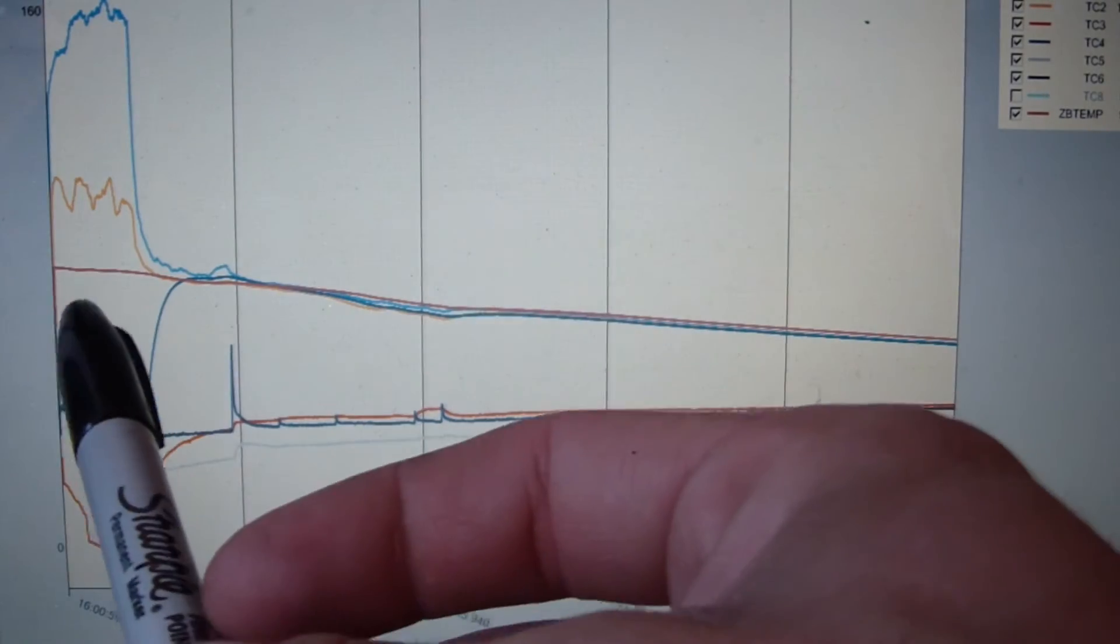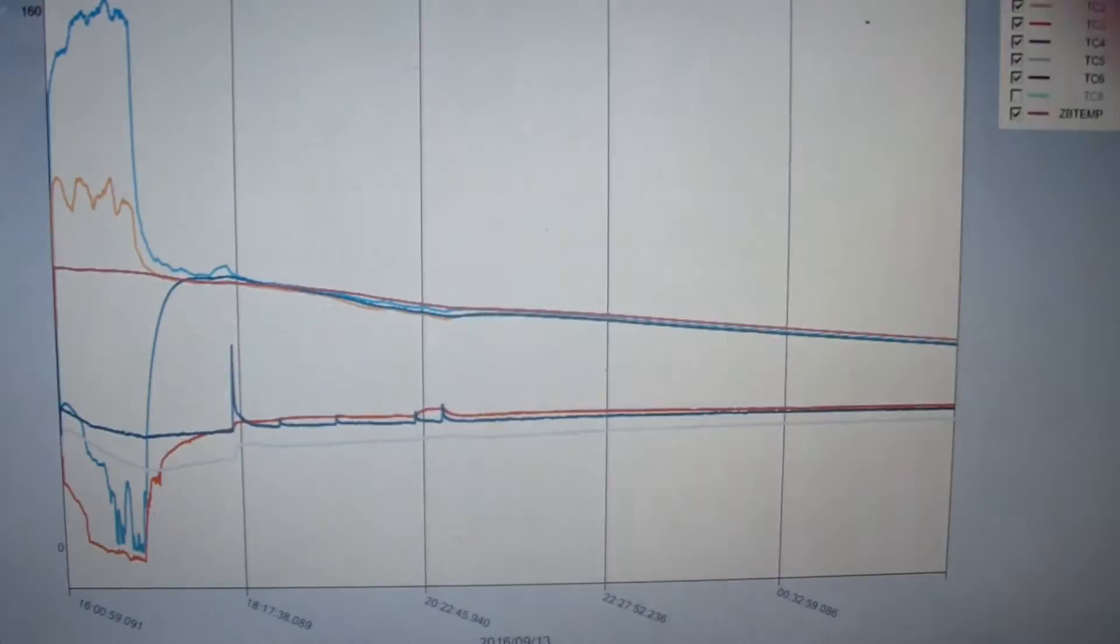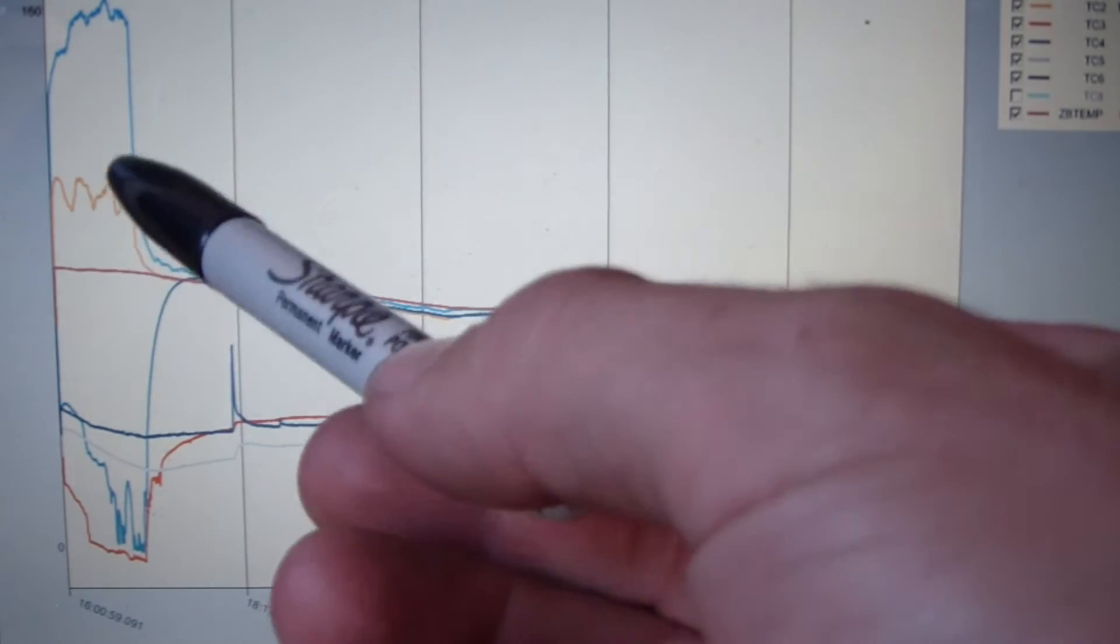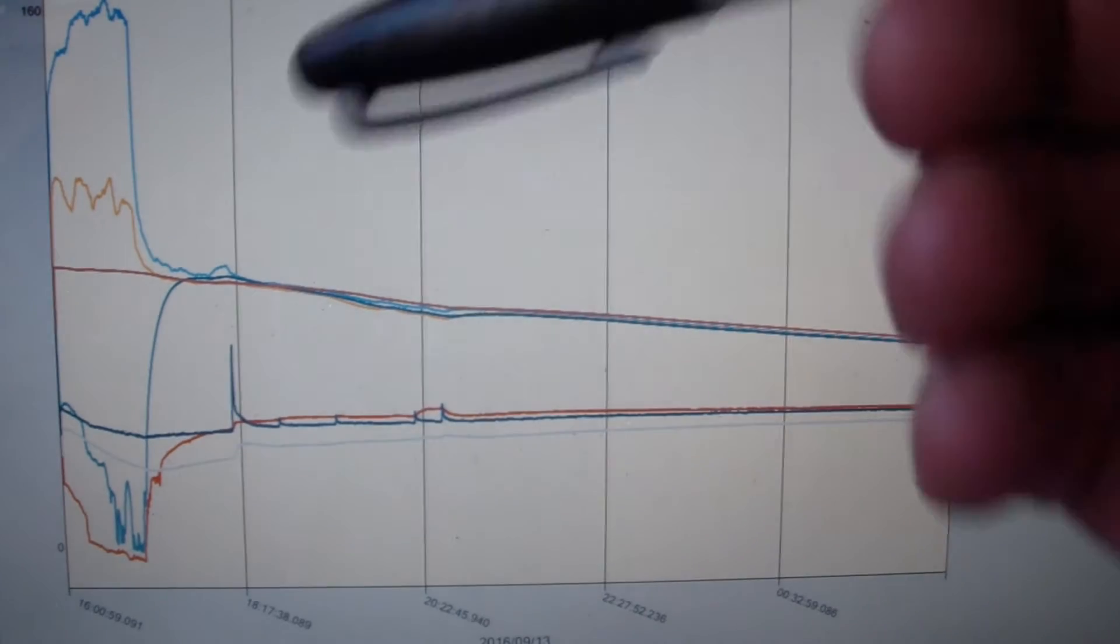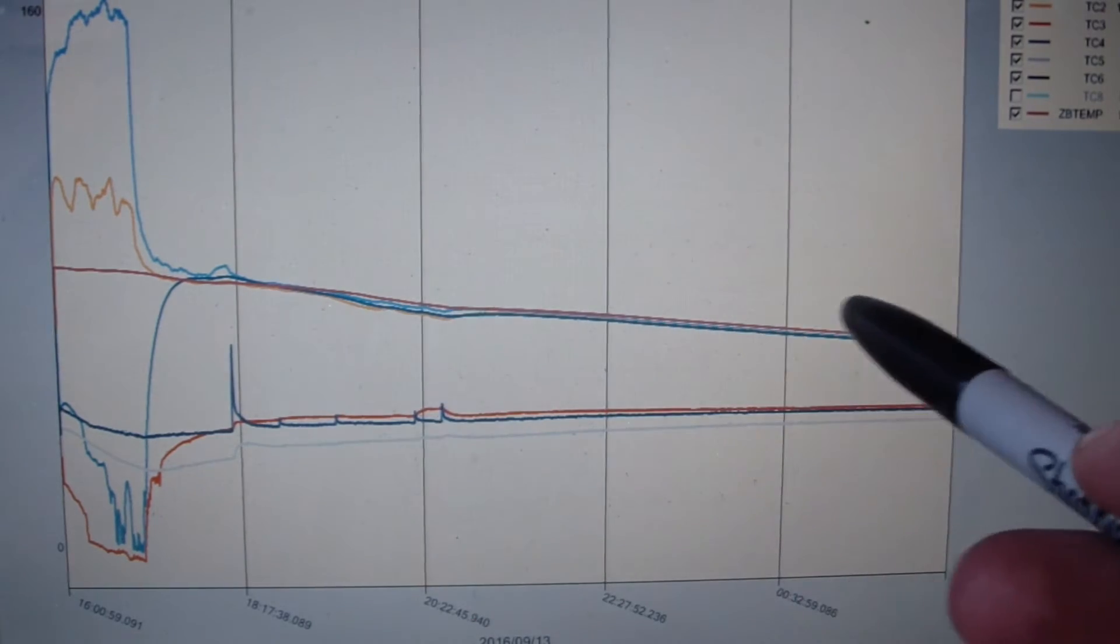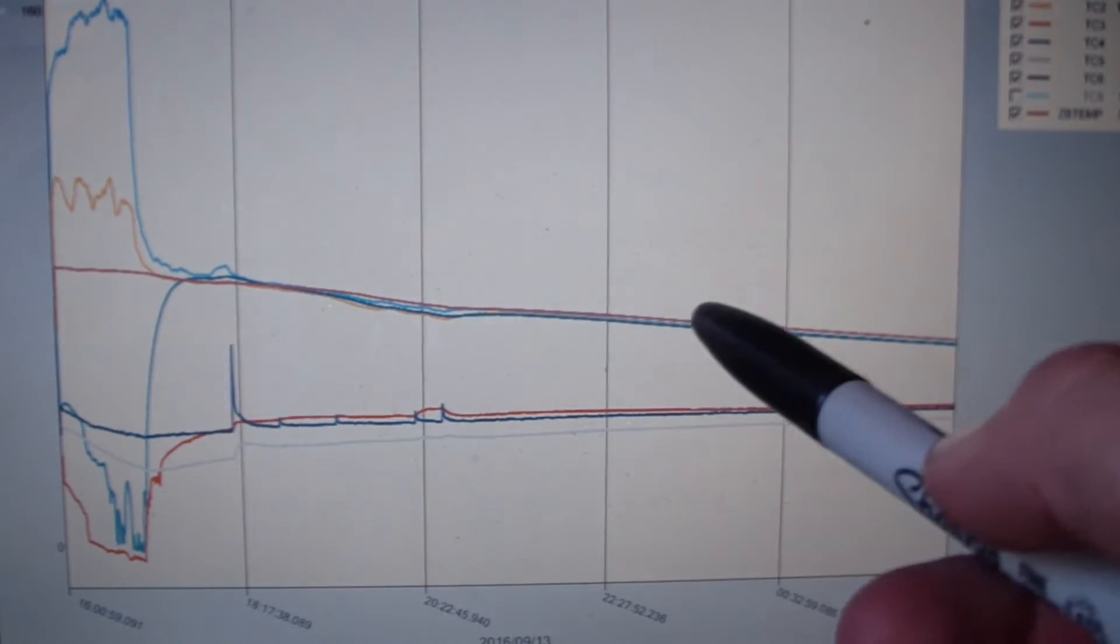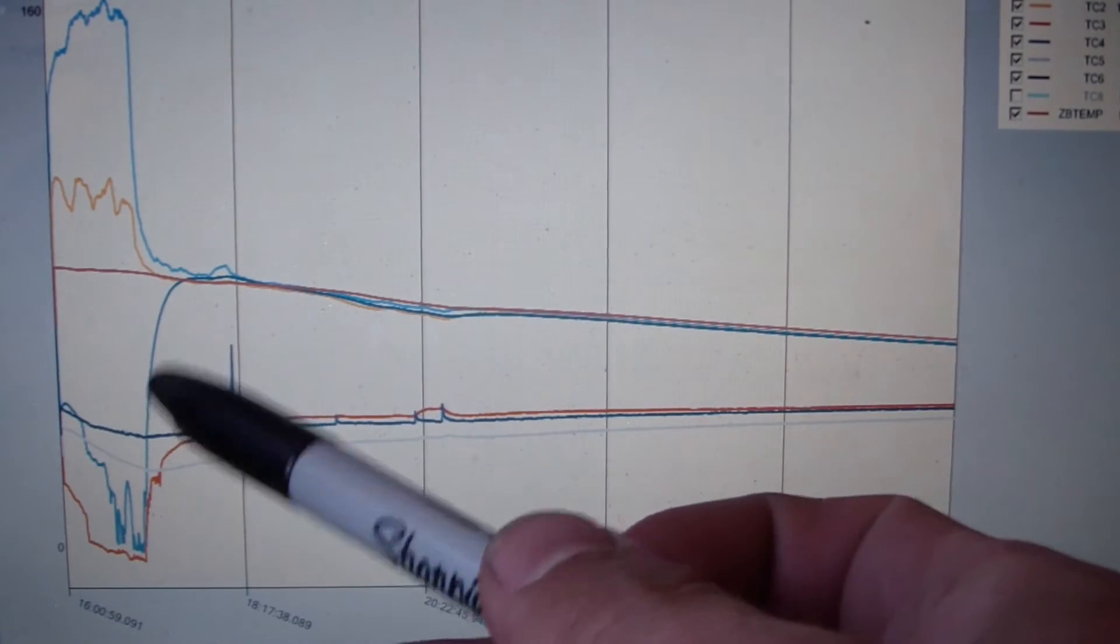You see these little squiggles here? The top mark right there, the blue one, that's superheat discharge. Then the one below it, that is the subcooling. Notice that the sawtooth there, that's the wind. Whenever the wind blows across the condenser it cools a little bit better.